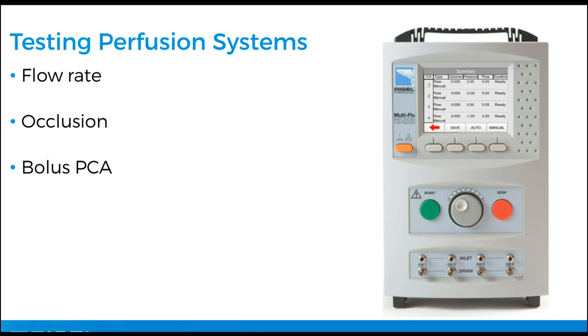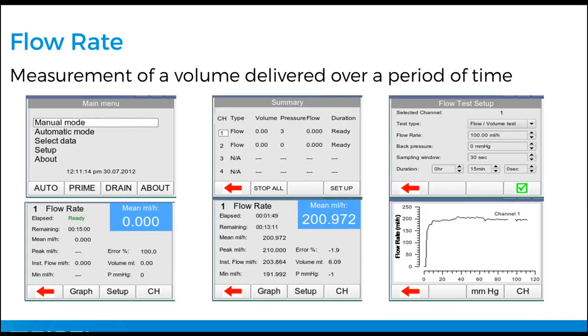So what are we testing? What's offered? Testing with the multi-flow, we have flow rates, we have occlusion, and we have bolus patient-controlled analgesia. So flow rates, we have both manual and automatic mode, so we can set up within an automatic mode. If you have a service manual and you have a test setup for various flow rates, you can do that sequentially.